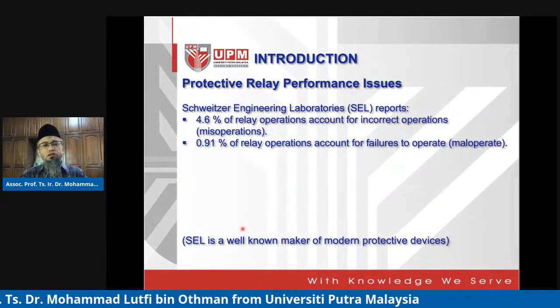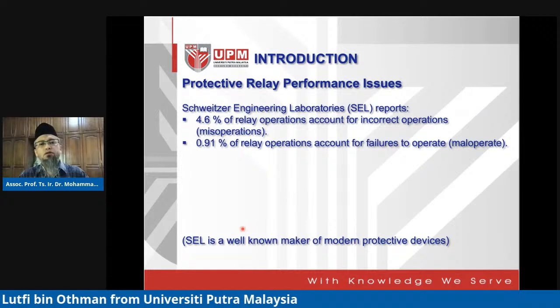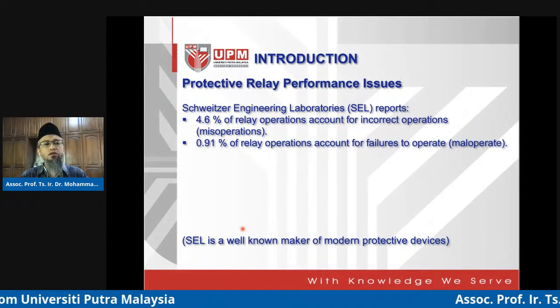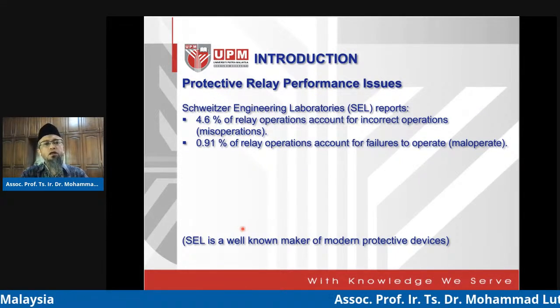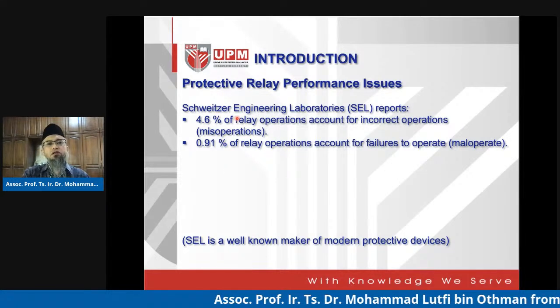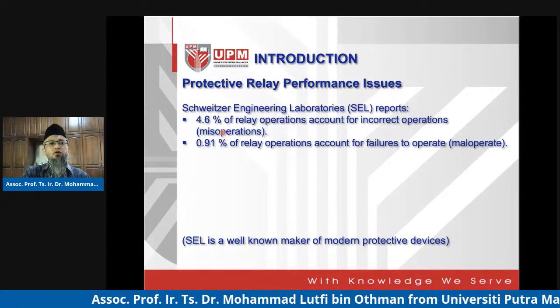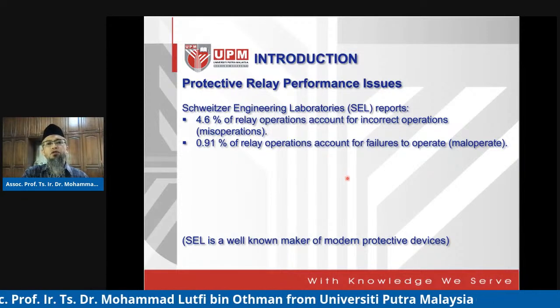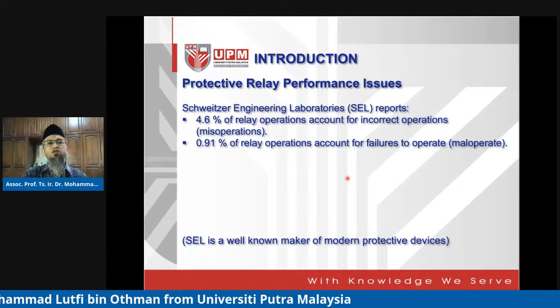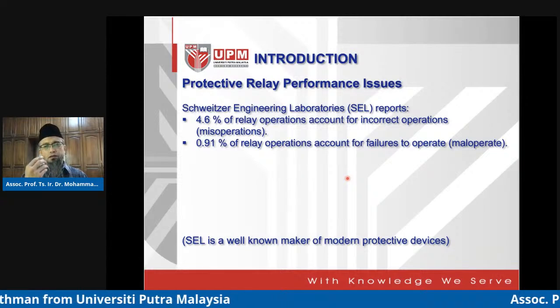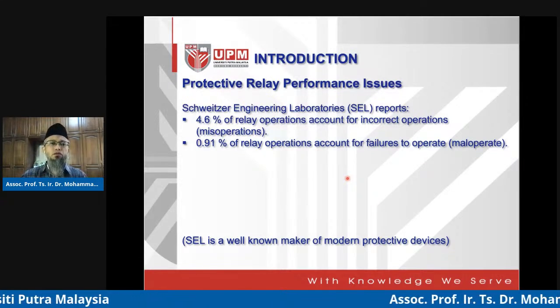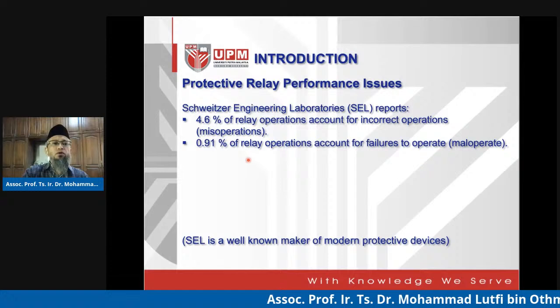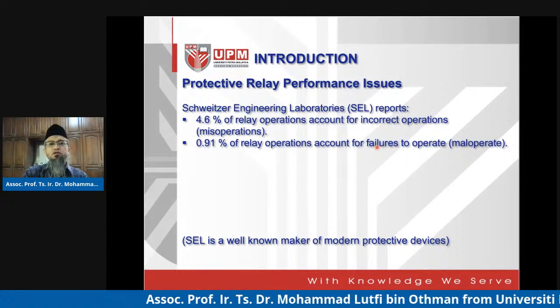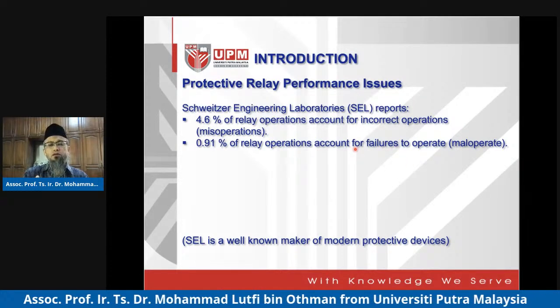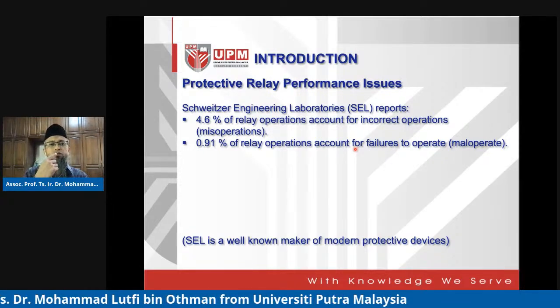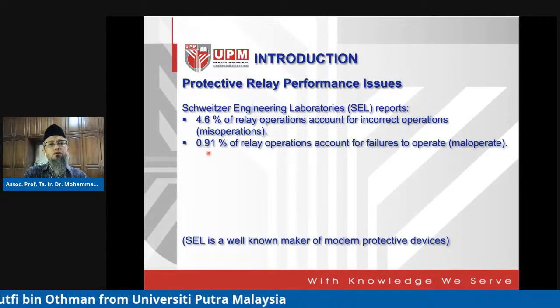As far as understanding the performance of relays, it has been mentioned by one of the very famous makers, familiar to us, SEL, Schweitzer Engineering Laboratories, that 4.6% of relay operations account for incorrect operations, or what we call misoperations. The relay operates, but it's operating incorrectly, so we call it a misoperation. Whereas mal-operation, which is basically failure to operate, where it has to operate but does not, accounts for almost 0.91%.